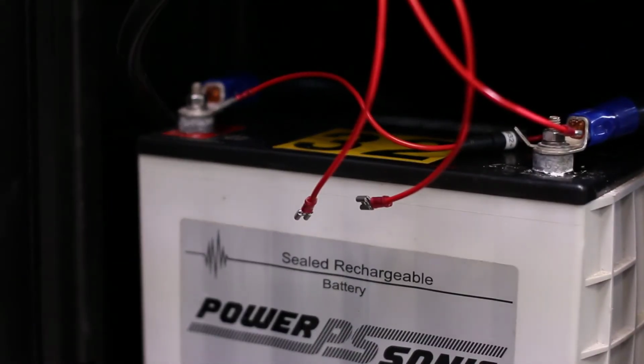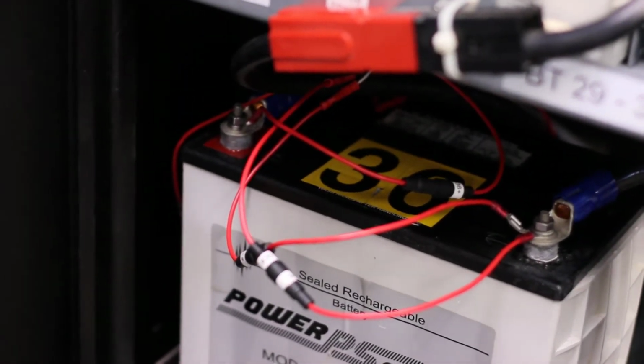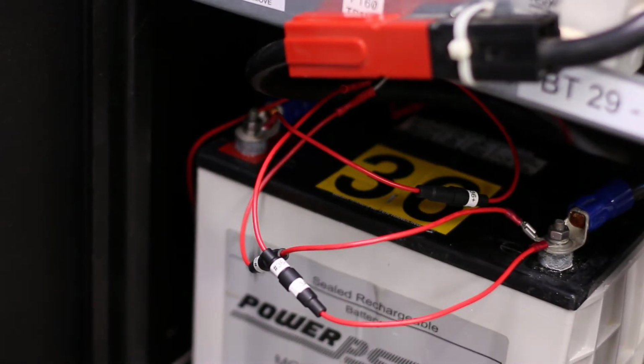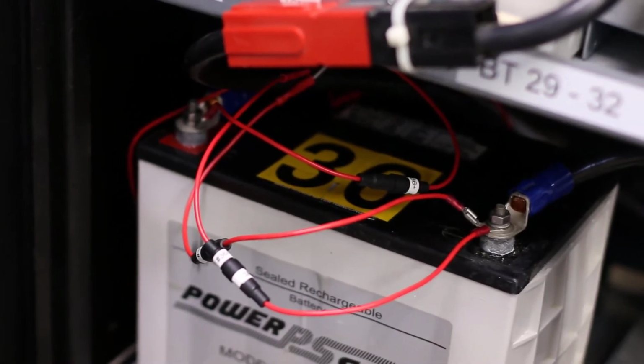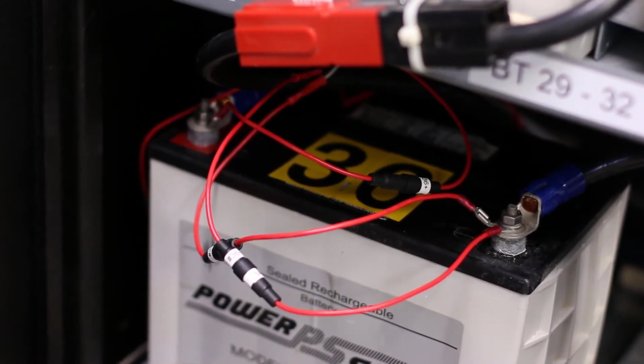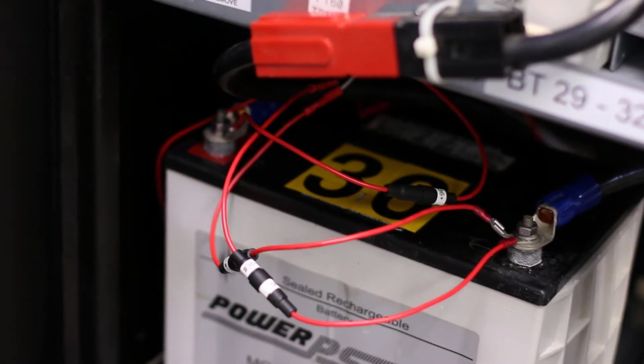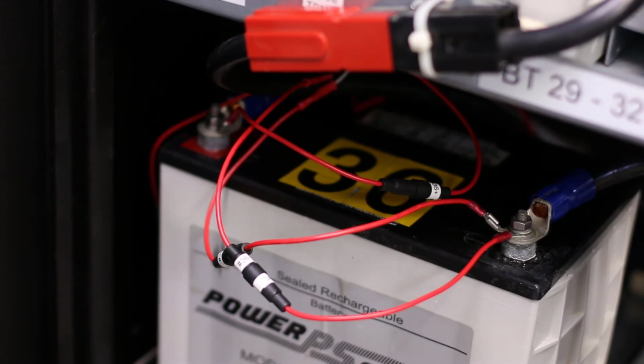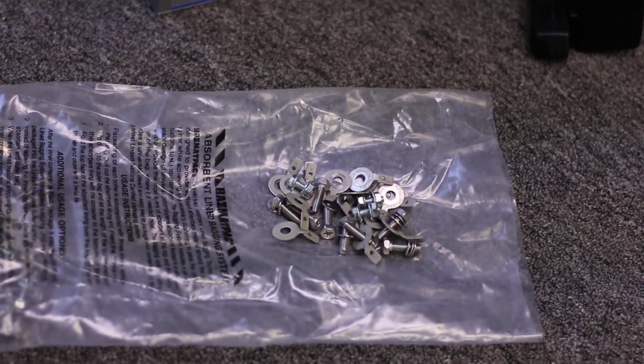There are 3 special ones that go to the very positive, the very negative, and the middle point. Those 3 fuses are 3 amps, for the internal resistance measurement current. For some existing batteries, the terminal may only have 1 connection, so we may need to unscrew this terminal and put the O-ring on this connection. We cannot share 1 tab for both the measurement and the internal resistance current. So that's the battery types.